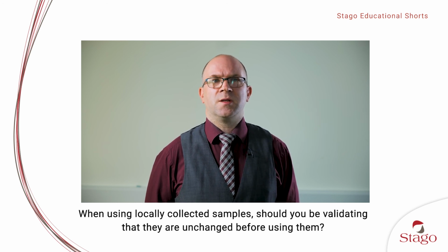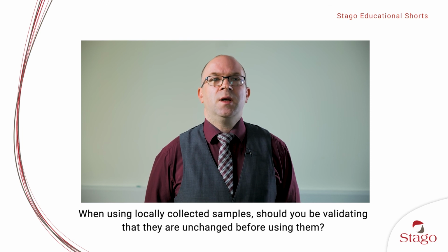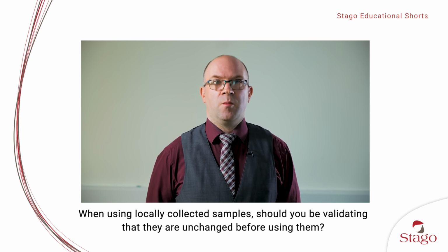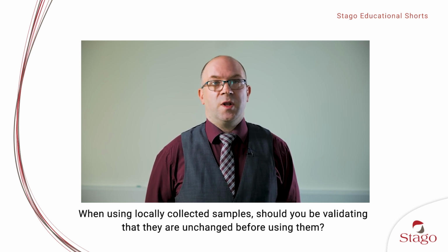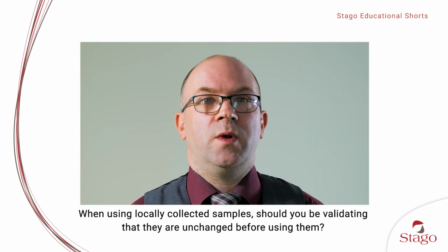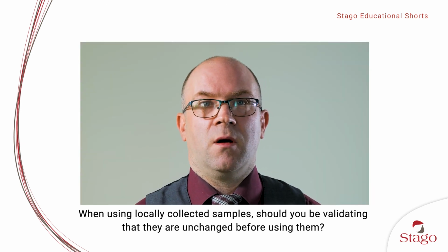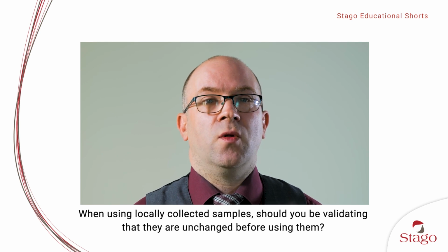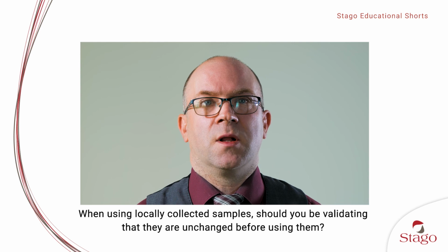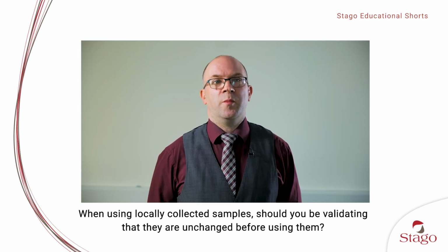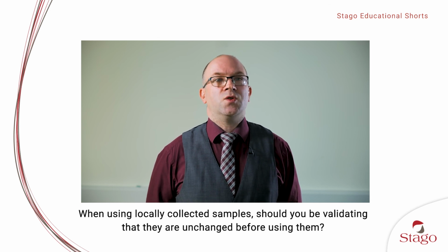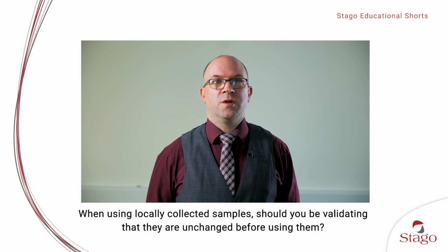So when you're doing comparisons, as I said in the presentation, things have got to be consistent, run at the same time, samples run at the same time, handled in the same time, thawed if necessary at the same time. We need to ensure that all pre-analytical variables are accounted for and controlled for, so that we are verifying across the same thing. Because the last thing we want to do is to have to implement a lot of corrective actions and raise non-conformances and do things like that because of things that we've not controlled for ourselves in the laboratory. So we need to verify that what we are doing, handling of the specimens, is consistent.